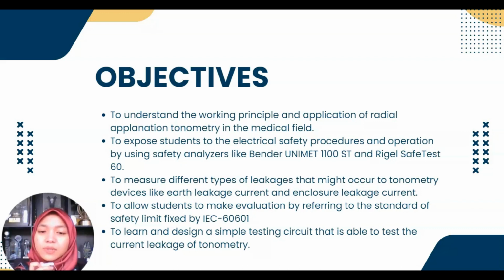Third, to measure different types of leakages that might occur to tonometry, like the earth leakage current and enclosure leakage current. Fourth, to allow students to make evaluation by referring to the standard of safety fixed by the IEC 60601. And the last one is to allow the students to design a simple testing circuit that is able to test the current to detect the leakage of the tonometry.